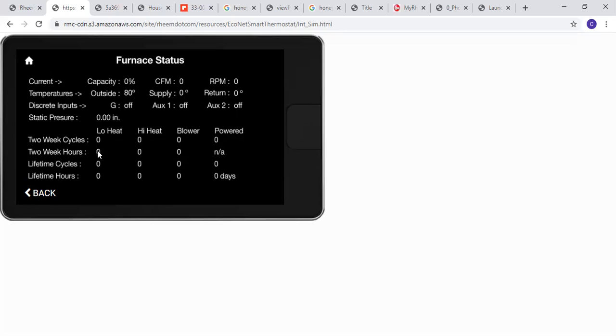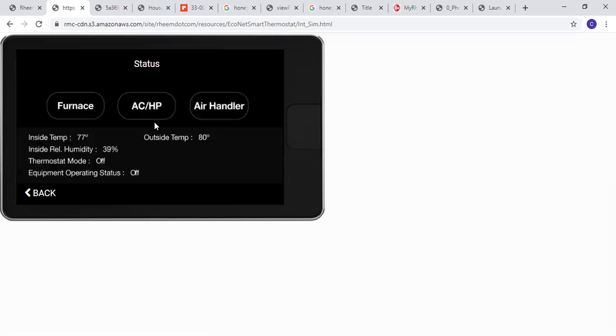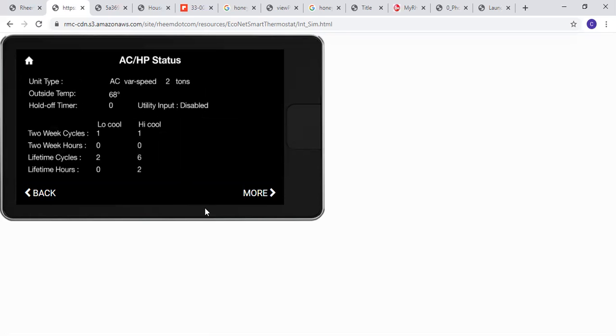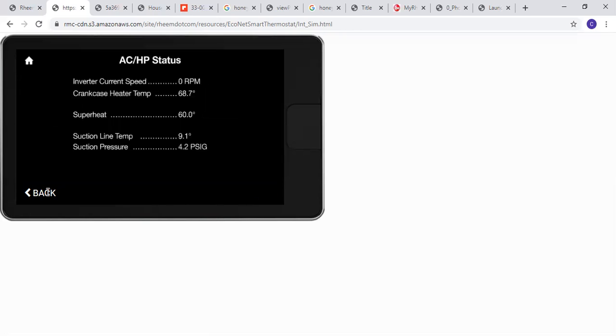So it will give you your static pressure, give you your cycle counts here, give you your capacity, your CFM, your RPM. If you're using supply or return air temperature sensors, it'll tell you that. Same with AC heat pump. So if you have an inverter system, this is where it gets real cool. You can actually check your inverter speed. It'll tell you what your RPMs are, crankcase heater, superheat, suction line temp, and suction line pressure.